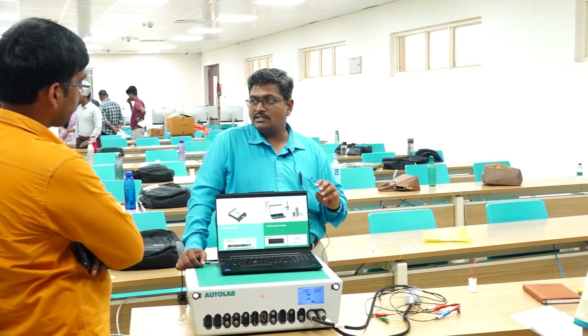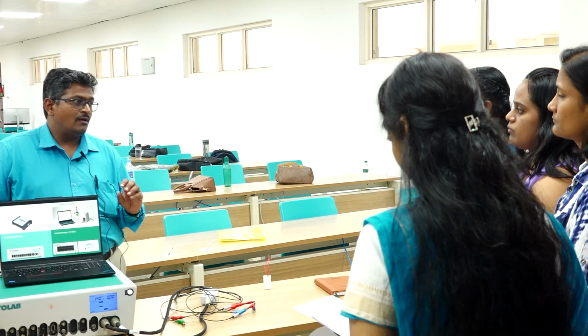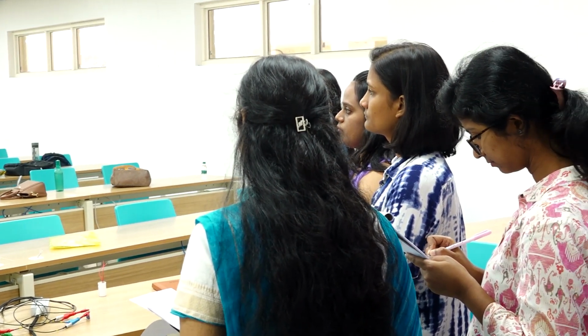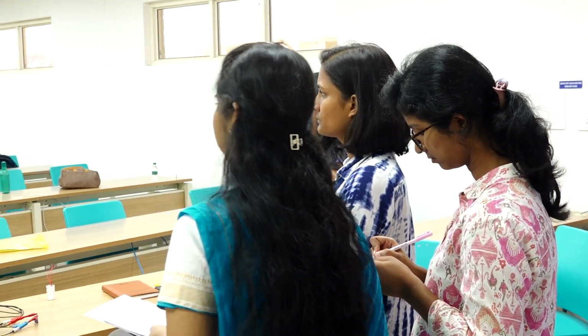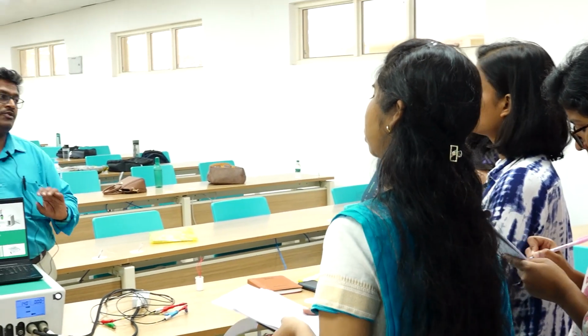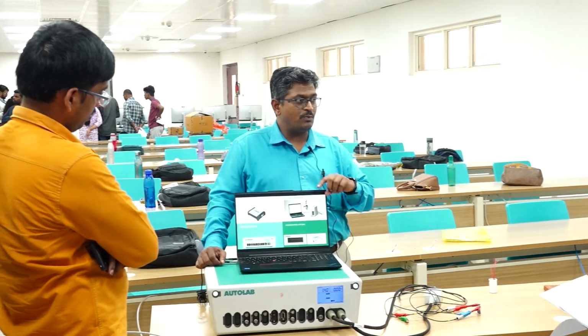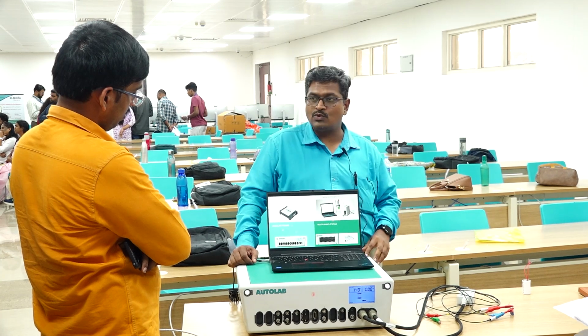For example, if your solution is consuming some 5 volt, but you want to apply 5 volt to your working electrode, the instrument will apply 10 volt, to compensate for your solution, and then exactly 5 volt goes to your working electrode. You are applying 5 volt, but the instrument is actually applying 10 volt. This 10 volt is called the compliance voltage.